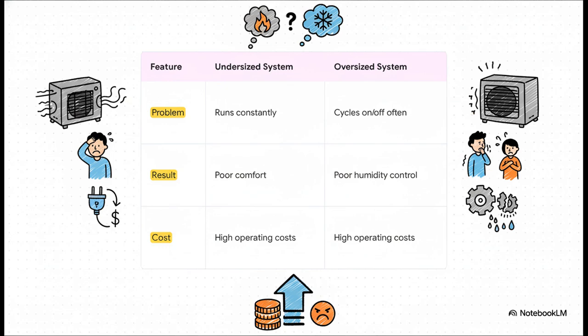This slide perfectly illustrates the problem. If your system is too small, it's going to run constantly, trying desperately to keep up. That wastes a ton of energy, and you're probably still not going to be comfortable. But if it's oversized, it'll blast your room with hot or cold air and then shut off really fast. That constant on and off cycling is super inefficient, puts a lot of wear and tear on the machine, and does a terrible job controlling humidity. Either way, you're looking at higher energy bills and a home that just doesn't feel right.